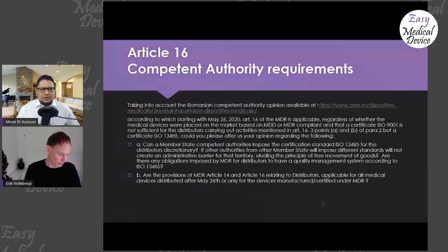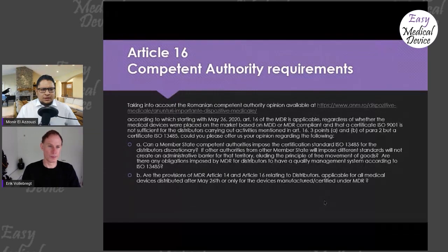So if I'm going for an ISO 9001 and I'm covering the requirements of translation and repackaging for the devices that I'm receiving, is it fine? The question is whether you can actually do this under an ISO 9001 certificate from a certification body.